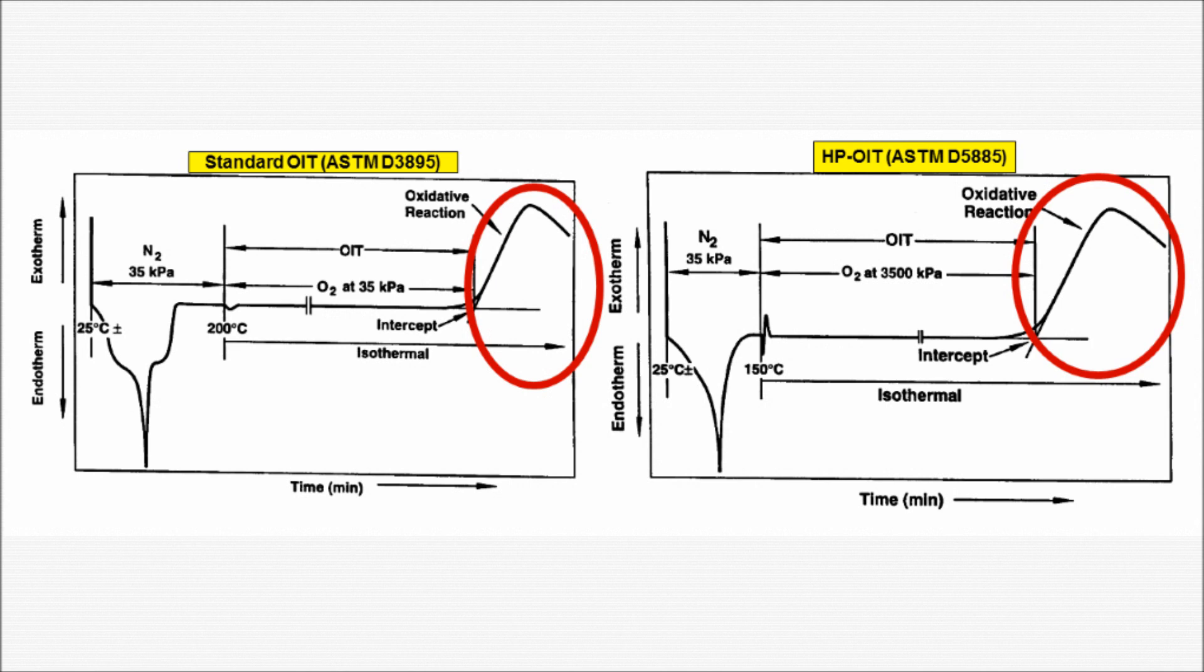Highlighted now is the exotherm for both graphs. As you can see, the heat flow ramps up to reach a peak, and then begins to fall. Once the peak has clearly been overcome, the test may be stopped.